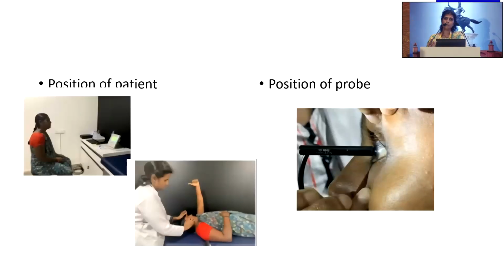And fixation of the patient is very important. Keep the other hand or other finger of the patient fixating, or the light coming from the A-scan probe as a fixating modality. Always hold the fixation probe from the wire and not the probe itself.